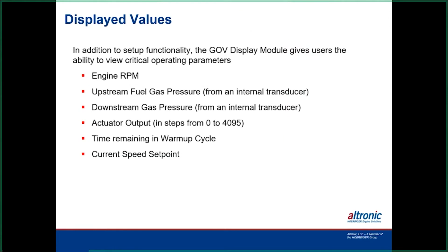So the display itself will read the RPM of the engine. It will read the fuel gas pressure and also the fuel supply pressure. The actuator output number is like a stepper valve that we have on our EPCs, but this one runs from 0 to 4,095. So it's got a lot of area in there as this poppet moves back and forth.